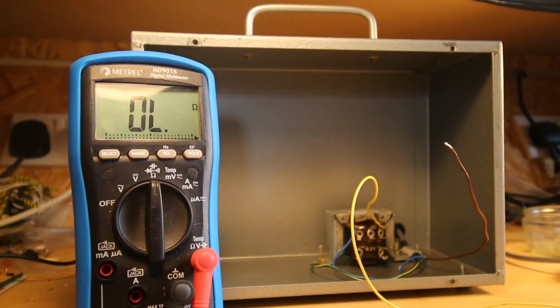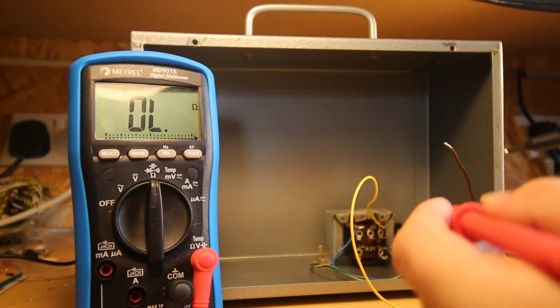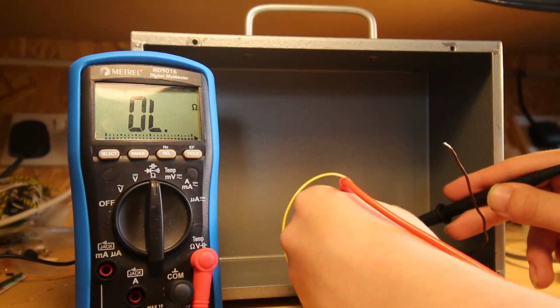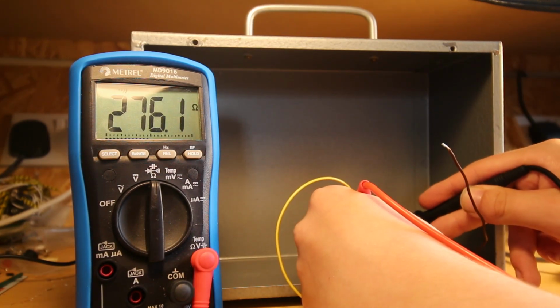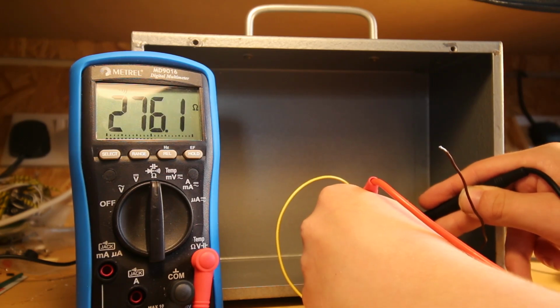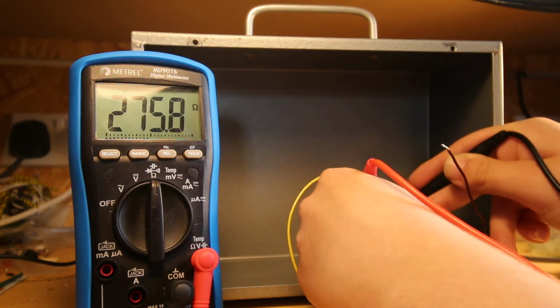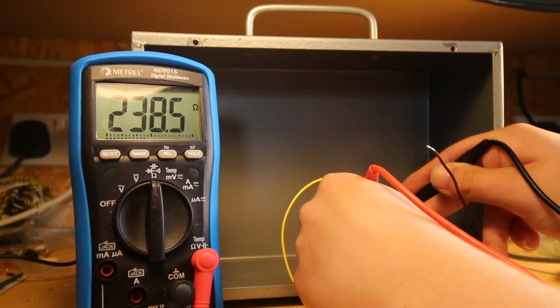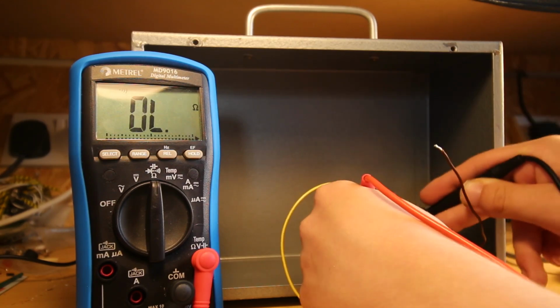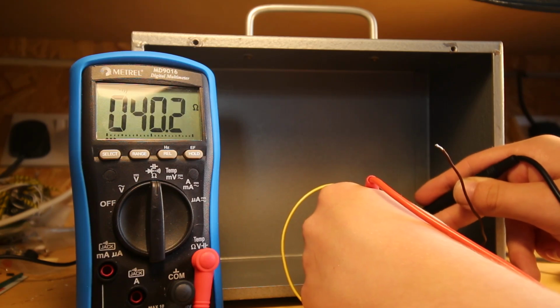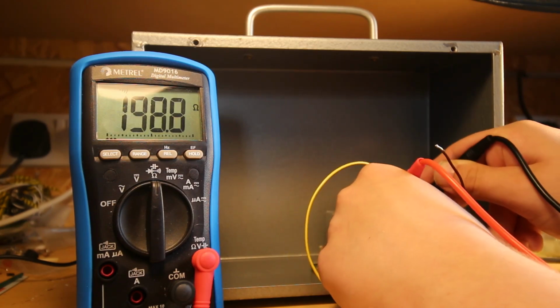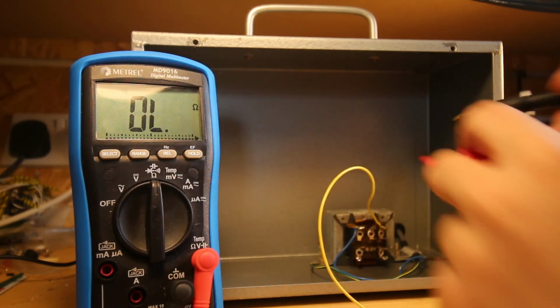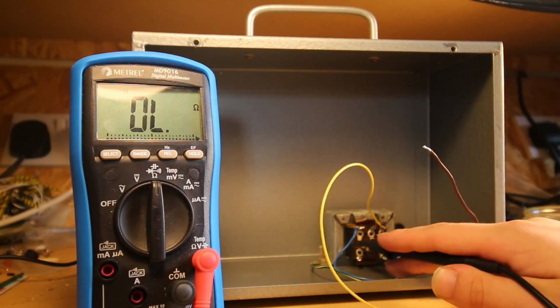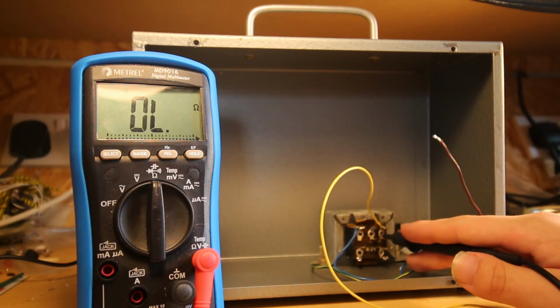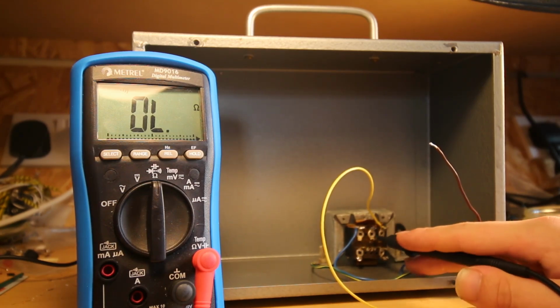What I'm going to do is I've got my multimeter on continuity. I'm just going to check that the primary is actually continuous and the secondary is continuous and they're not shorted together. So if we measure from one of the primary to the other, we get 277 ohms-ish. And the centre tap, we get 230 ohms, and that one, we get, this is not reading clearly, but about 37 ohms. So what this probably is, it's probably 0, 230, 240, or 220, 240.